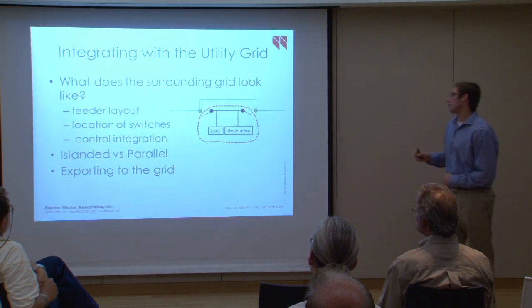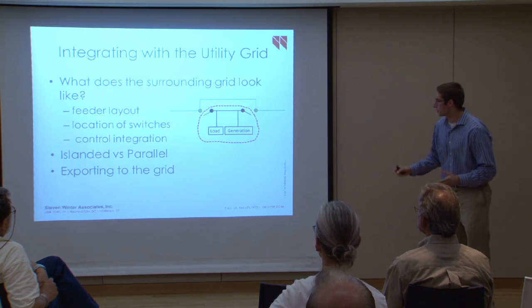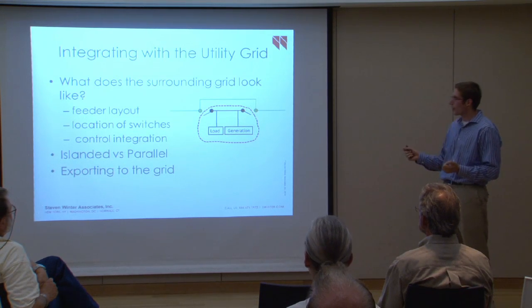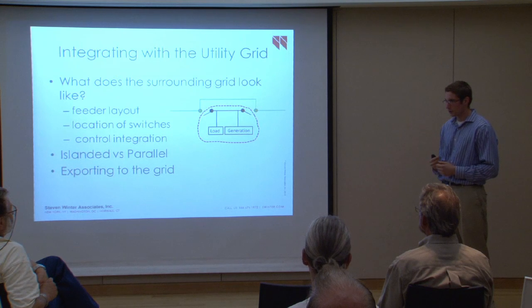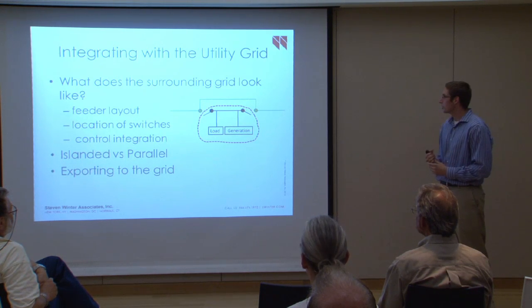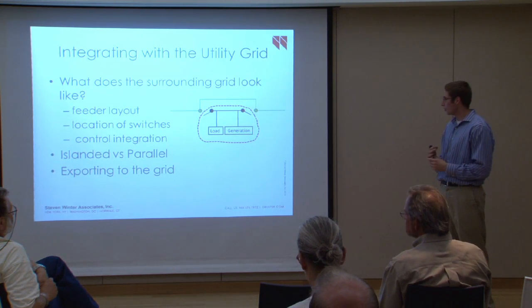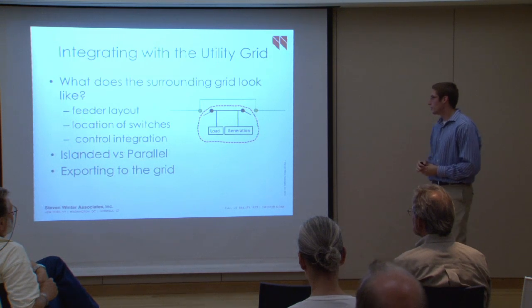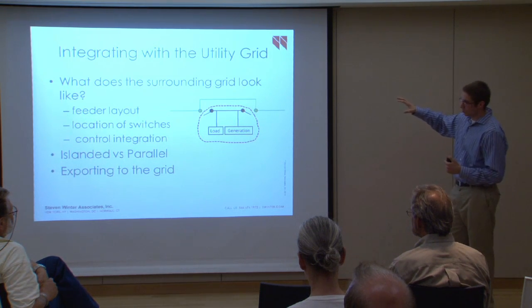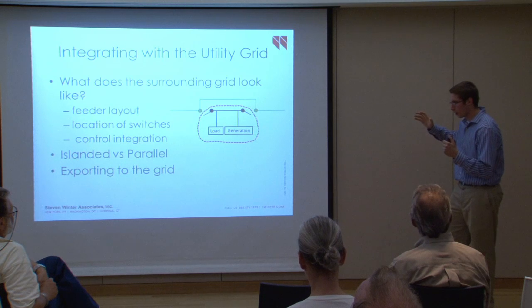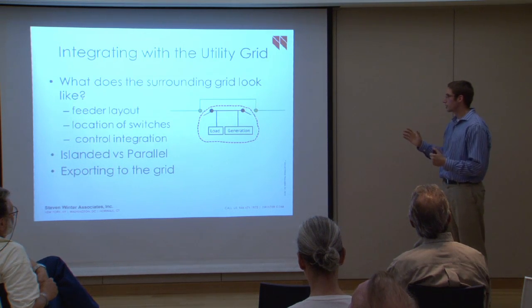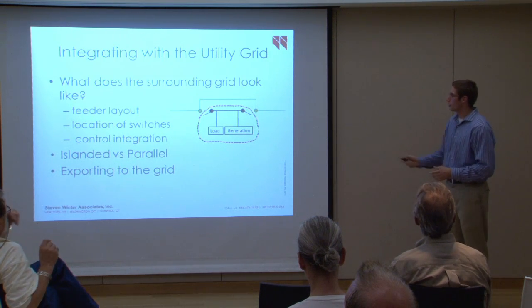So things you'll want to work with the utility to determine: what is the feeder layout, where are their current switches, are they available to use, and how will we control this? Ultimately what we want is to create a situation where we can operate our microgrid so that it's in parallel with the grid.